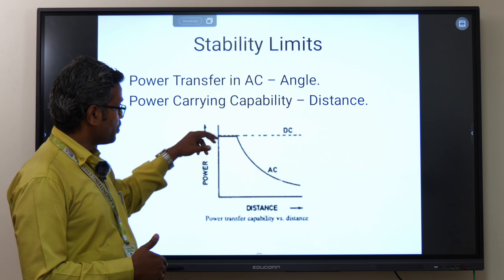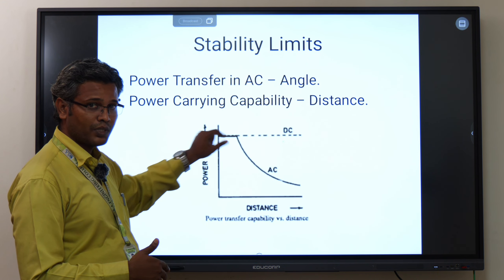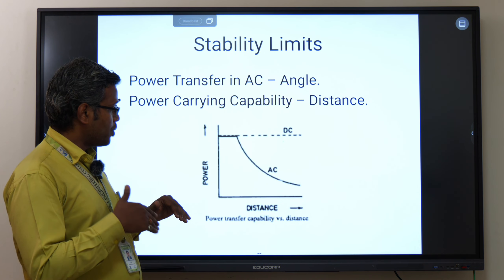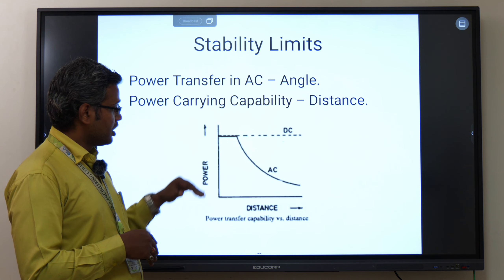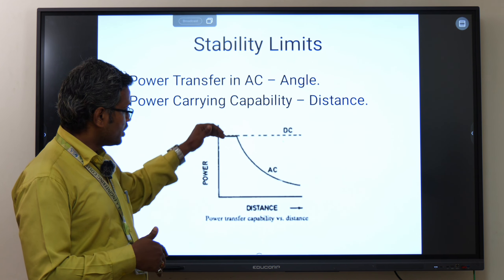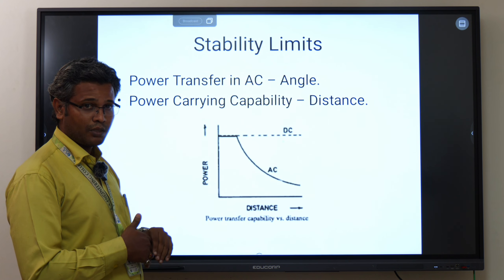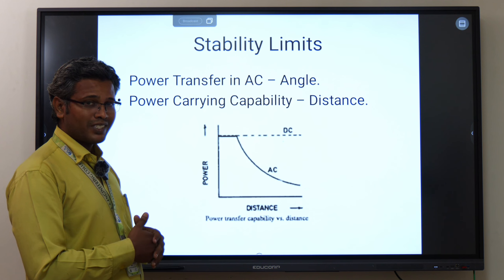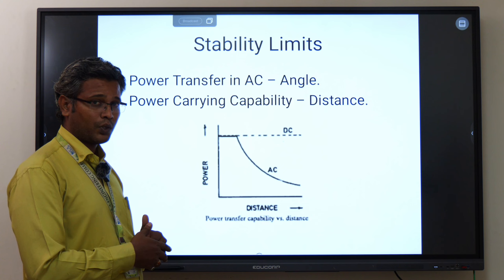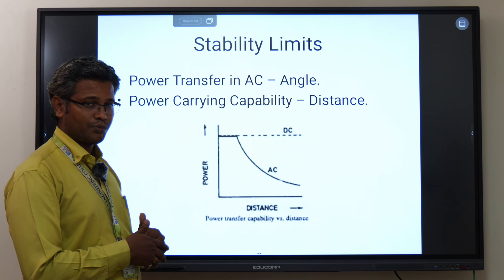For AC, up to a certain limit — termed as the surge impedance load — the power transfer capability remains constant. Above that, as distance increases, the power transfer capability declines. That is why we prefer DC transmission for long distances, as there are no stability problems in DC, whereas AC has stability limit problems for long transmission lines.